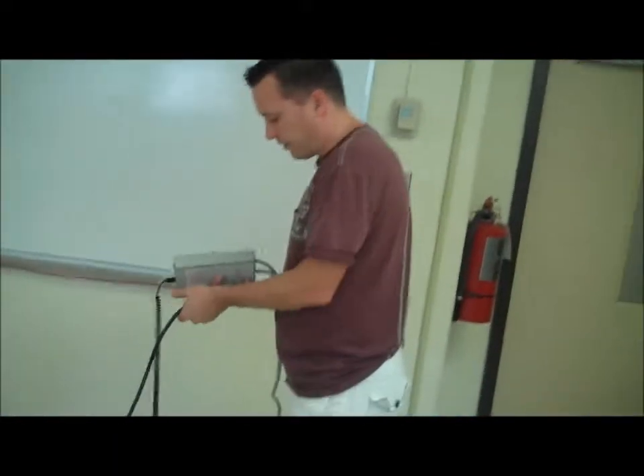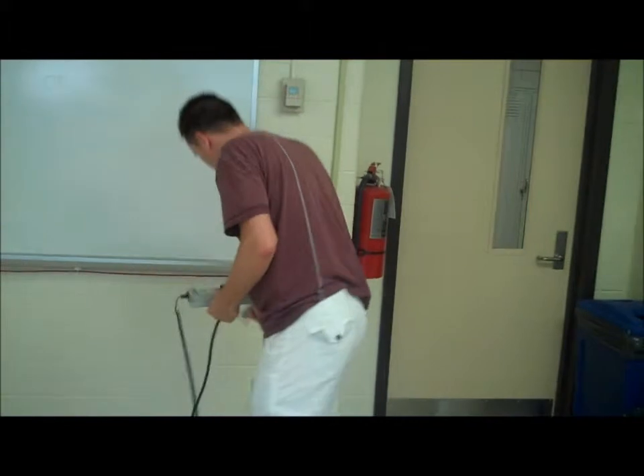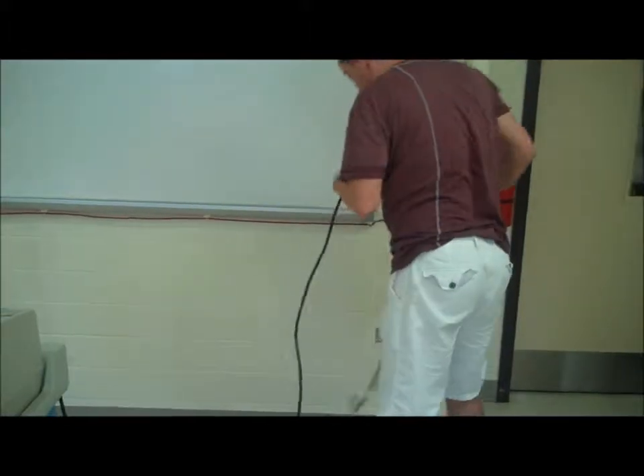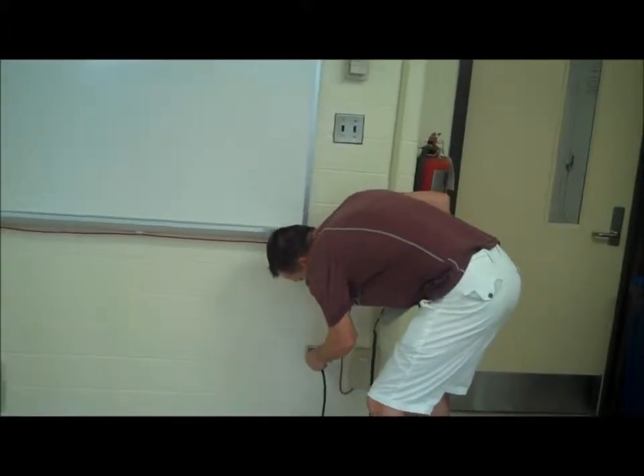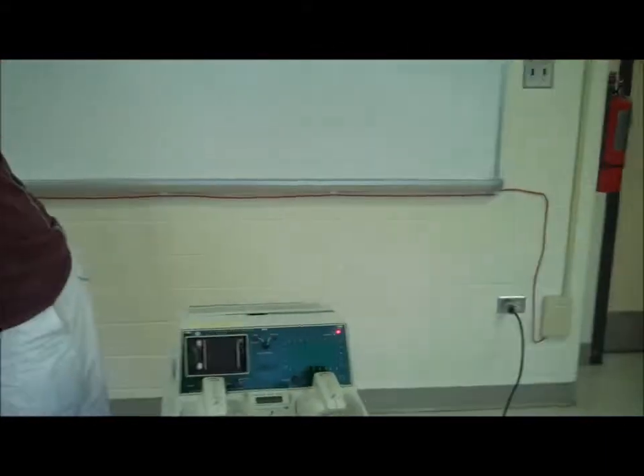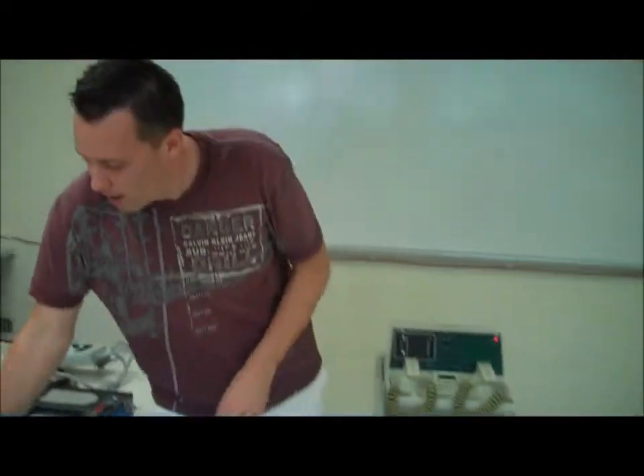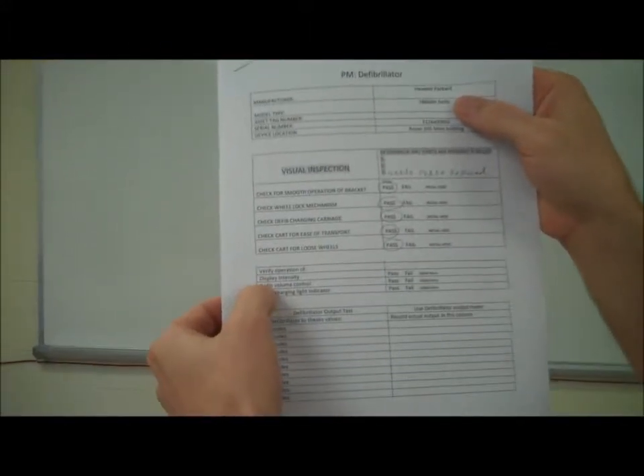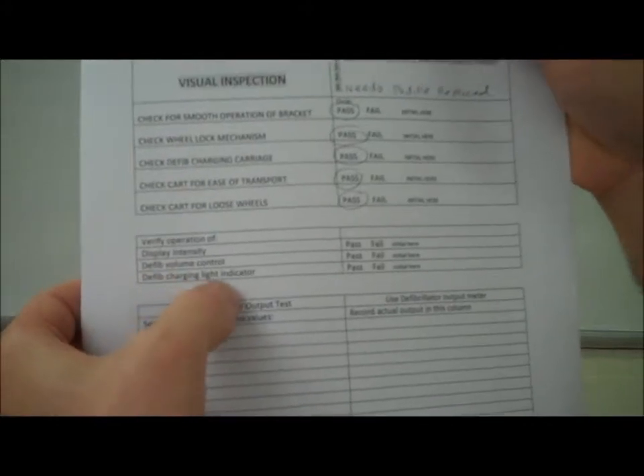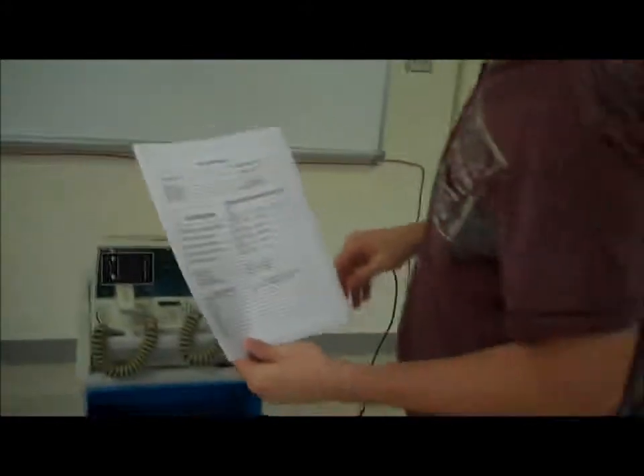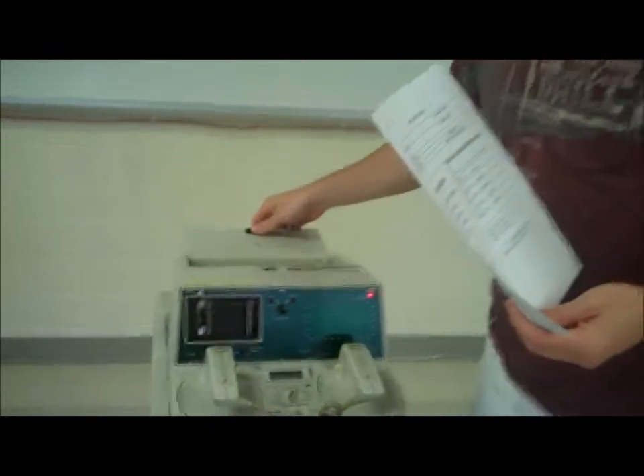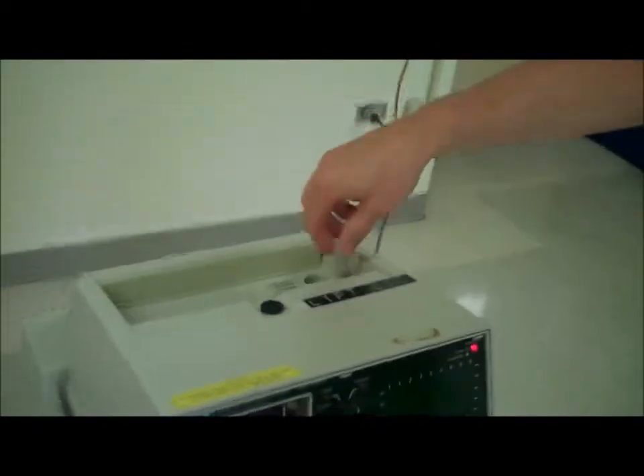Now we can unplug the device and plug the defibrillator back into the wall outlet. And on our PM sheet, we're going to check a few things. We're going to check the display intensity, the defibrillator volume control, and a defib charging light indicator.